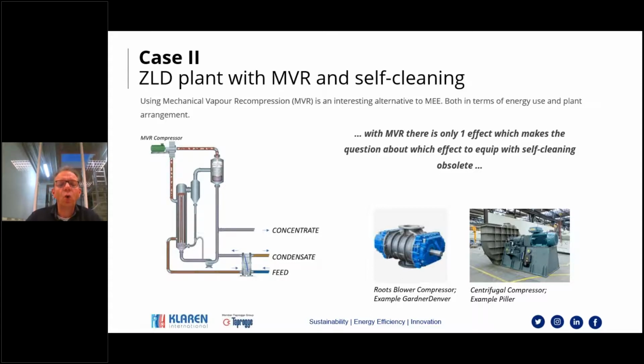In an MVR, all the vapor generated will be condensed in the same heat exchanger. But this heat exchanger can only work if this vapor is then of a higher temperature, because otherwise you have no driving force to transfer the heat from the shell to the tube side. So how do you get to a higher temperature? Well, you can do that by increasing the pressure, because if you increase the pressure, then the temperature at which it will condense at that pressure will increase. So that's the main principle.